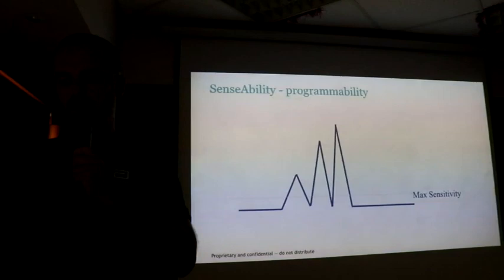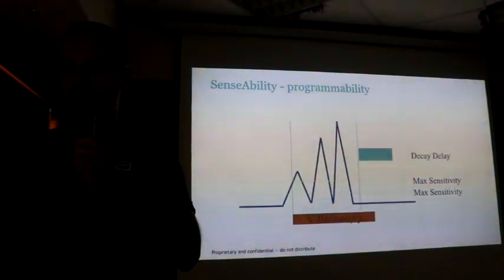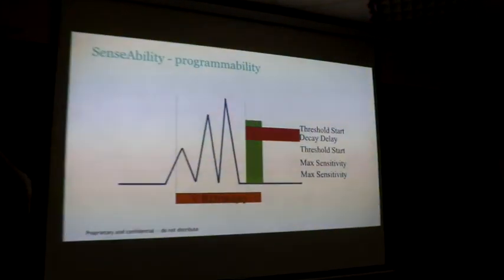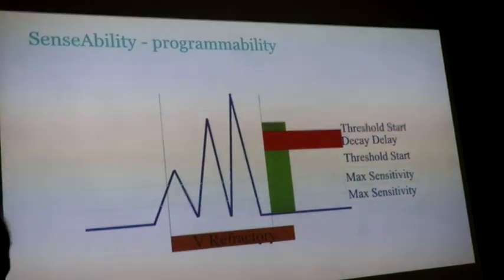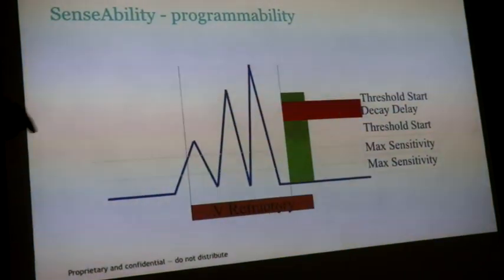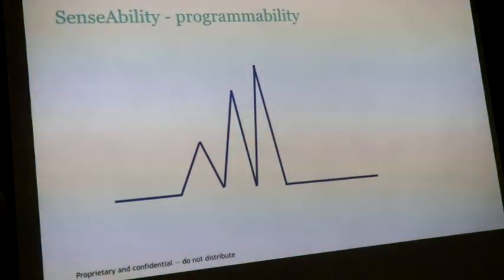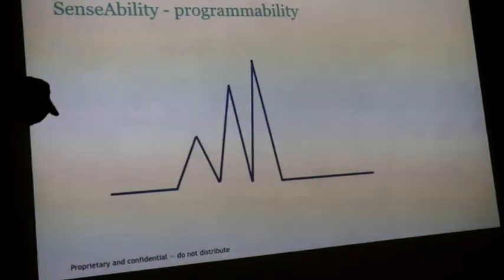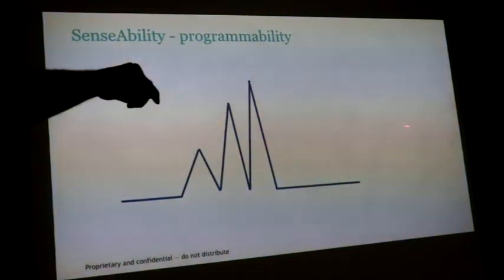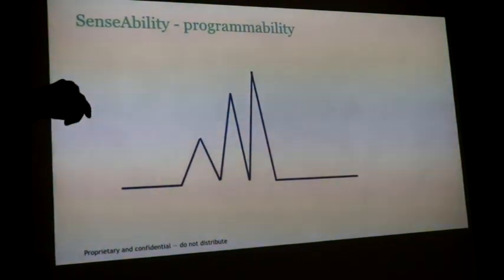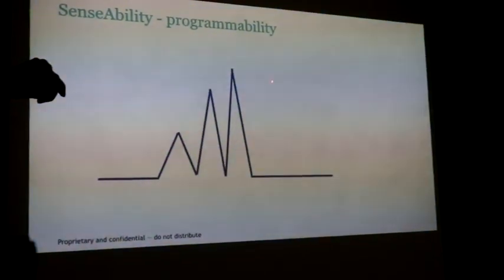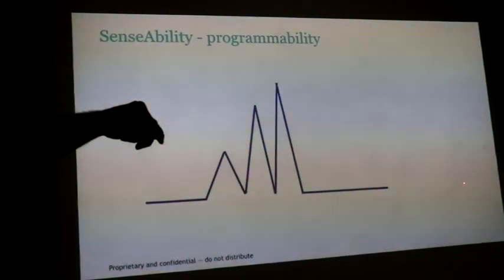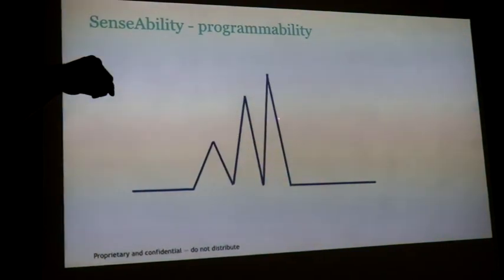So what we try to do today is use a slightly different sensing function, which is not fixed, so it responds to changing cycles and changing R waves. Let's look at a signal like this. With fixed sensitivity you just have a number and it runs like this, maybe 1 millivolt on a pacemaker atrial lead. We may get signals down here that are smaller. The automatic sensitivity function looks at the size of the signal, and it usually starts at about 50% of that size. So the sensitivity starts here, but instead of staying flat, it declines. So if you have changing signal amplitudes, this decline in sensitivity will pick them up. If the signal is this big, at 50% of it, it gets more sensitive.